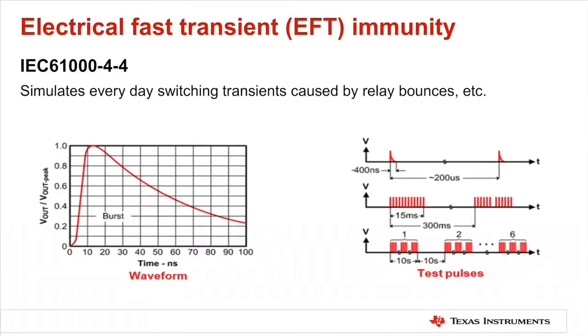IEC 61000-4-4 is the burst immunity, or electrical fast transient, test. Many manufacturers consider this test the most important, as it simulates everyday switching transients found in the industrial application space. It is performed on power, signal, and earth wires, or a subset depending on what is appropriate for the EUT. In this test, a burst generator produces a series of bursts lasting 15 milliseconds with a pulse rate of 5 kHz. The time between bursts is 300 milliseconds.